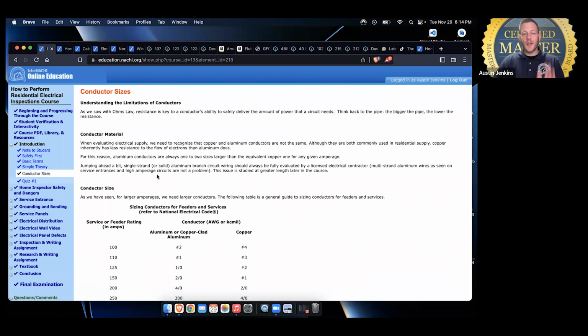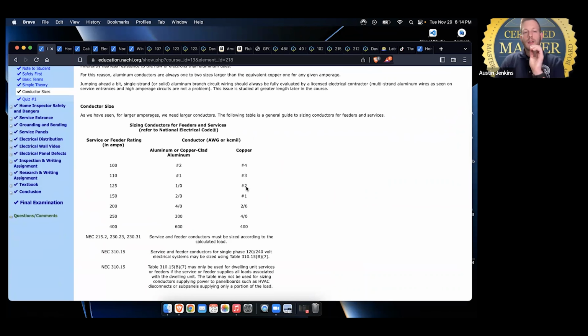So we're going to talk about conductor sizes really fast. Most modern homes—your typical one-to-four family residence—it's more of a standard to have a 200 amp panel utilizing 4/0 aluminum or 2/0 copper. Condominiums are the exception; I usually see condos between 125 and 150 amps.